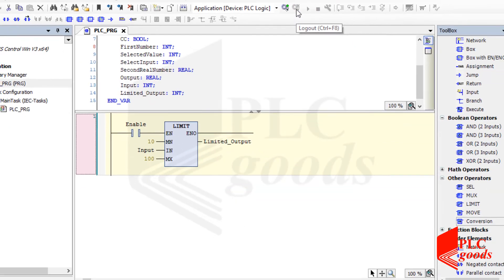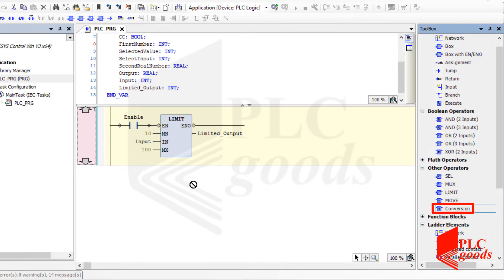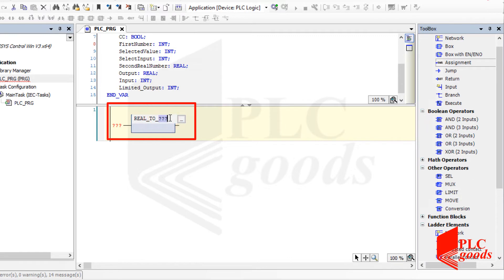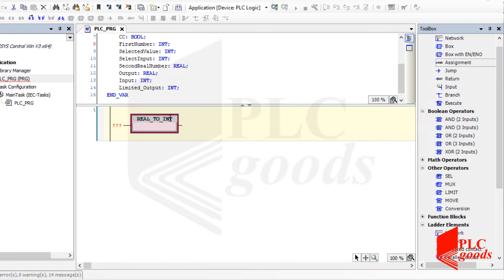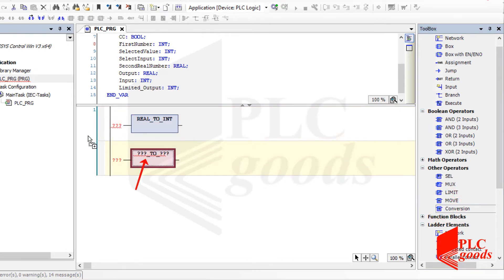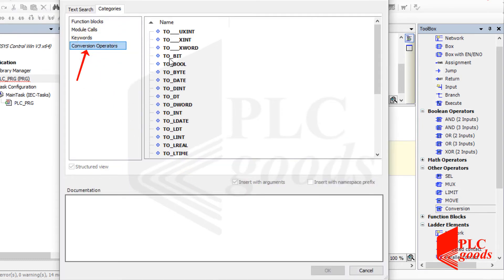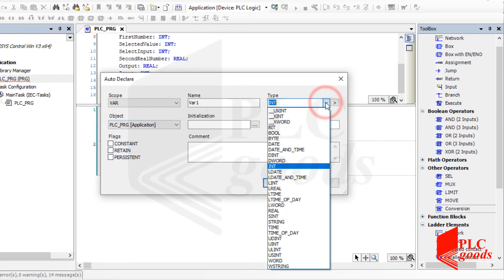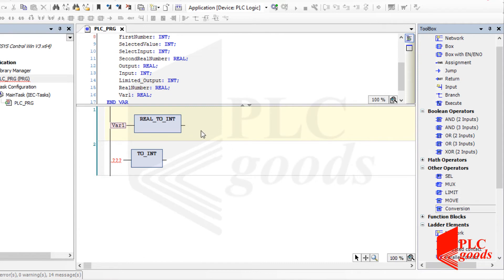The next instruction is move, which was explained in the previous video. The next one is conversion — it can change the data type of stored numbers. I'm going to use this instruction to convert a real number to an integer number; naturally its fractional part will be omitted. Instead of writing the conversion type, I can click here to find my desired conversion. For example, I'll select the one that converts the input to an integer. The selected data type for the conversion output is integer, not boolean, so instead of using coil models, the assignment item must be used.